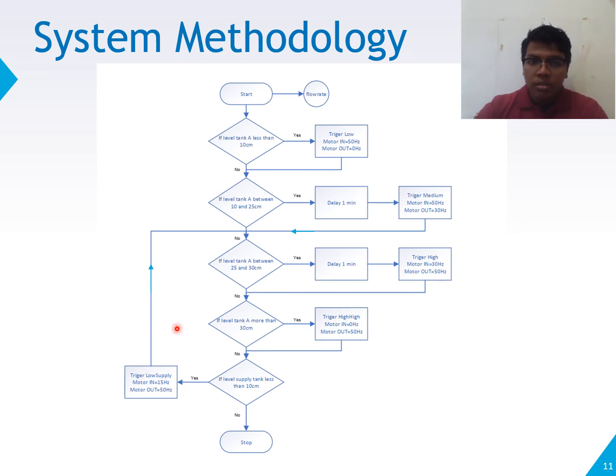An emergency feature is also included in the system whereby when the water level reaches 30 cm, all of a sudden, the program will trigger a high signal, thus adjusting the incoming motor speed to 0 Hz, while the outgoing motor speed is adjusted to 50 Hz to quickly lower the water level of the tank in order to avoid spillage. This is a very important feature as water spill may damage the components nearby.